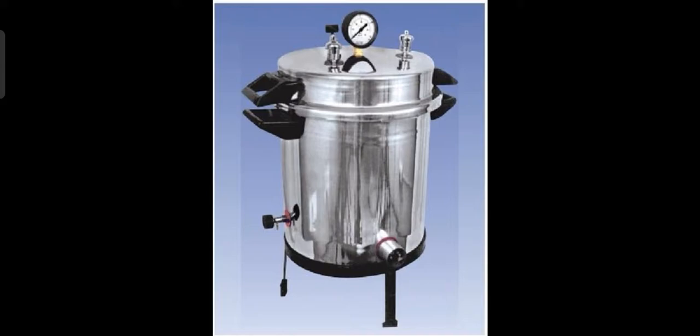What are the precautions that must be taken while using autoclave? The level of water should be checked before operating. The air should be completely evacuated from the autoclave, and the steam must have access to the materials to be sterilized. For example, if a material such as cotton, wool, or glass beads is to be sterilized in a glass bottle closed with rubber stopper, the sterilization would not be complete as steam cannot pass through the rubber stopper.